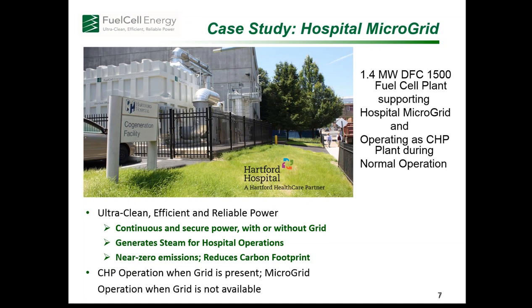So what is the advantage of that? You've got the fuel cell, which operates as a CHP attribute all the time. So even when the grid is there, which is almost all the time, the unit is generating power, saving the customer money relative to buying power from the grid. It also generates steam using the waste heat from the fuel cell.